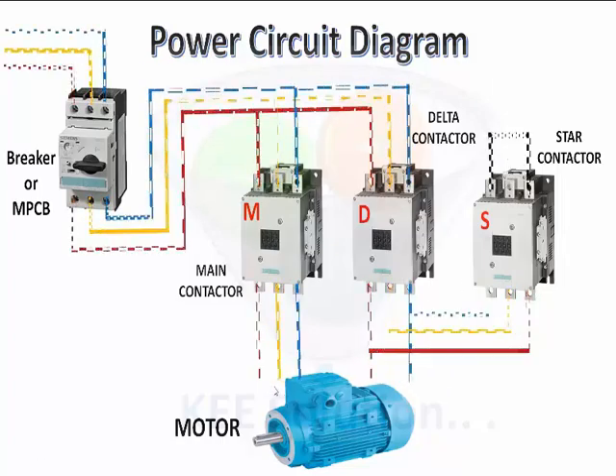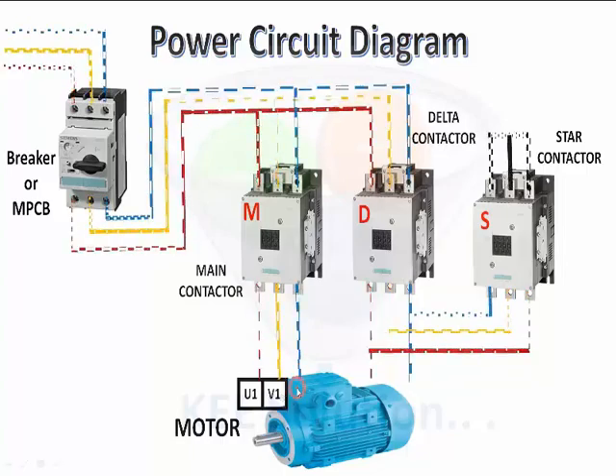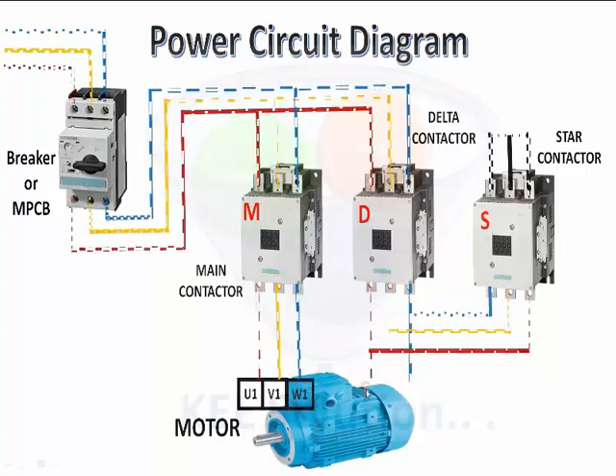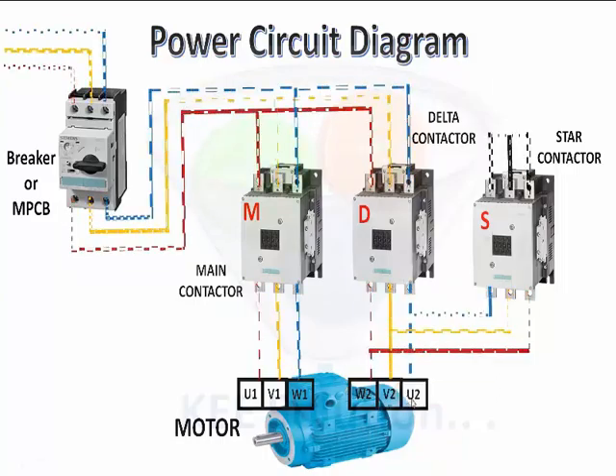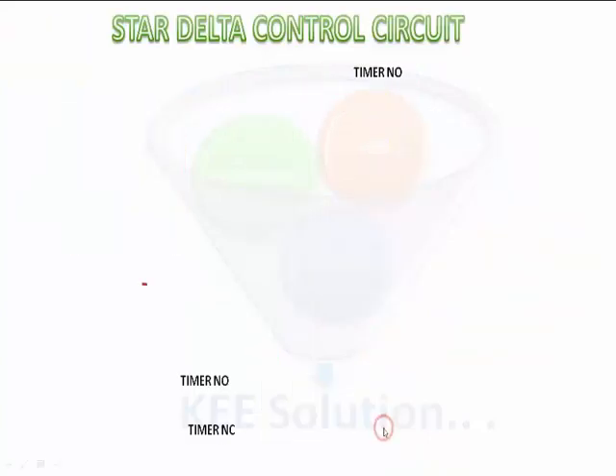So U1, V1 and W1 terminal connections of the motor will be made here. It is important that W2 of the motor connects to red, V2 to yellow, and U2 to blue.